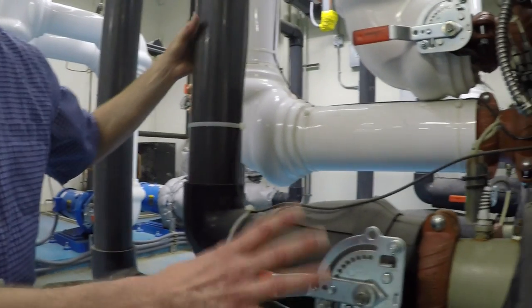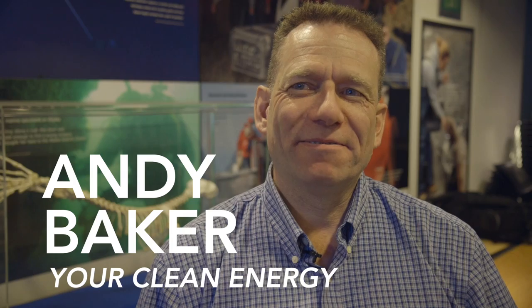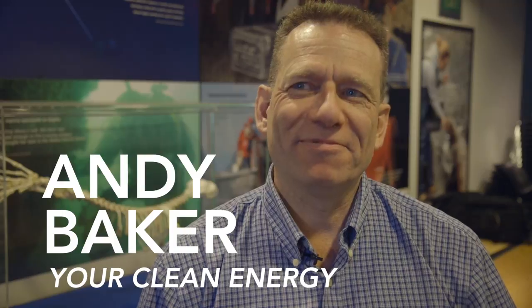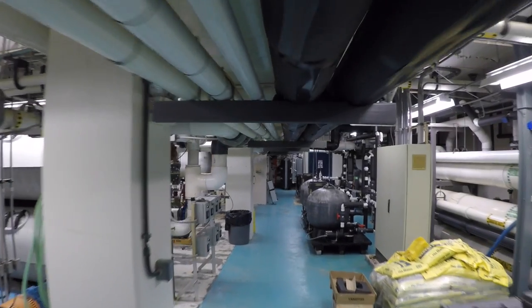That's Andy Baker. His Anchorage-based company, Your Clean Energy, designed and installed the heat pumps at the aquarium. Most people would say 52 degrees doesn't seem very hot. While it feels cold, especially if you swam in there, for a heat pump they like to see source temperatures of 35 degrees or warmer.